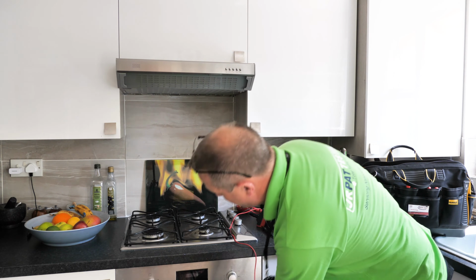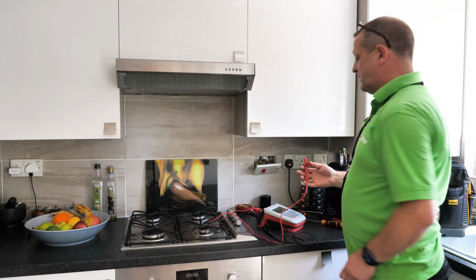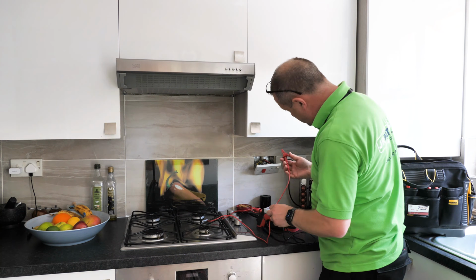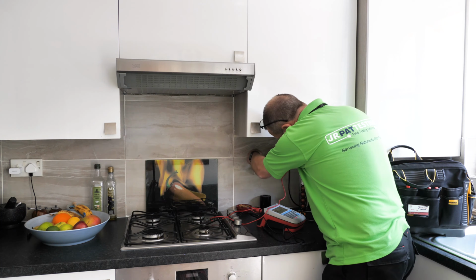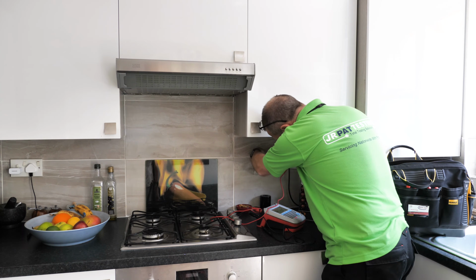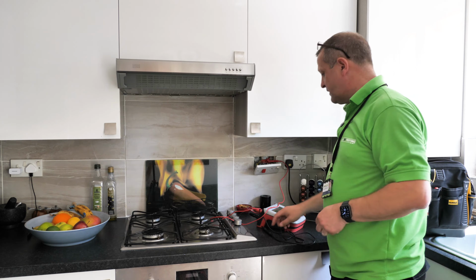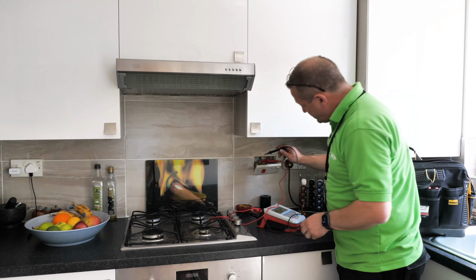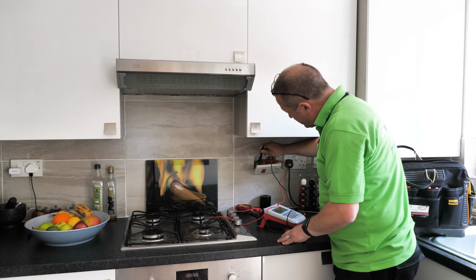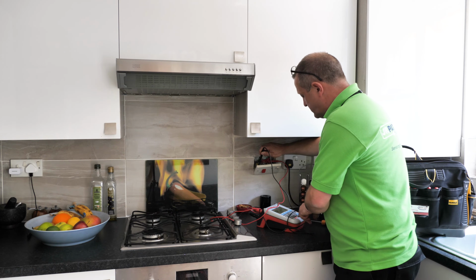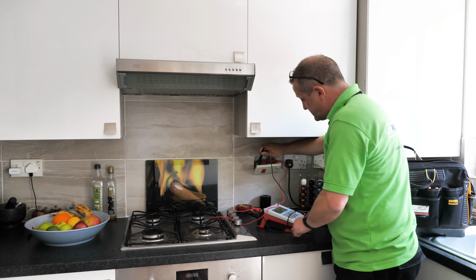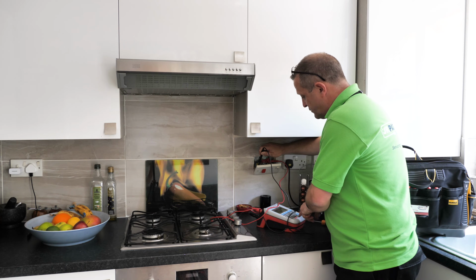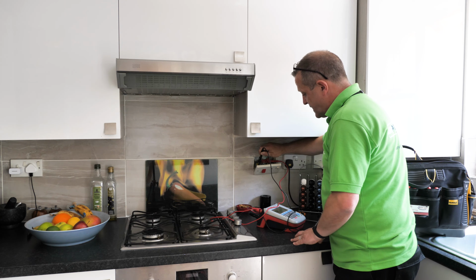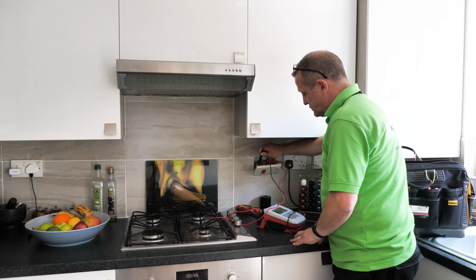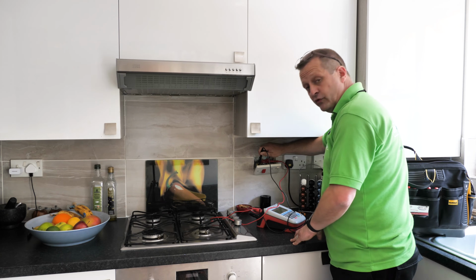So we take the crocodile clip that we'd use to connect to a metal part of the cooker, and we link the live and neutral connections, and again we use the probe on the earth part of the socket to conduct the insulation resistance test. Again, it asks me to make sure that everybody's safe from the system. Conduct the test to give its result, and again that's showing a good resistance level.